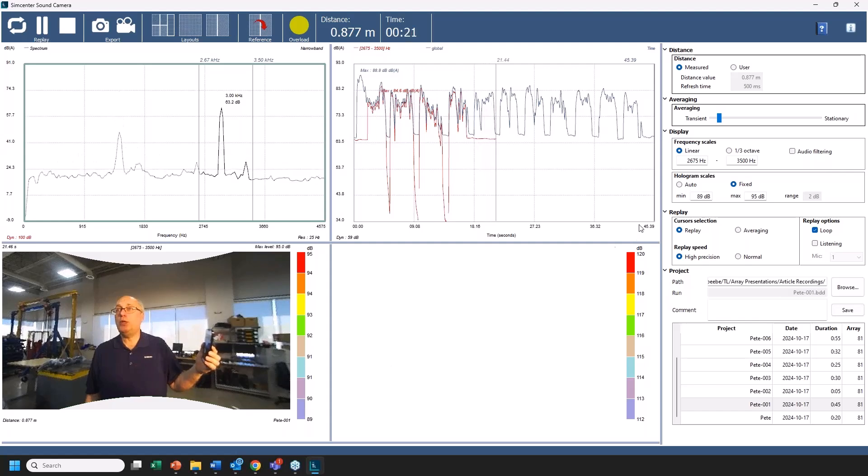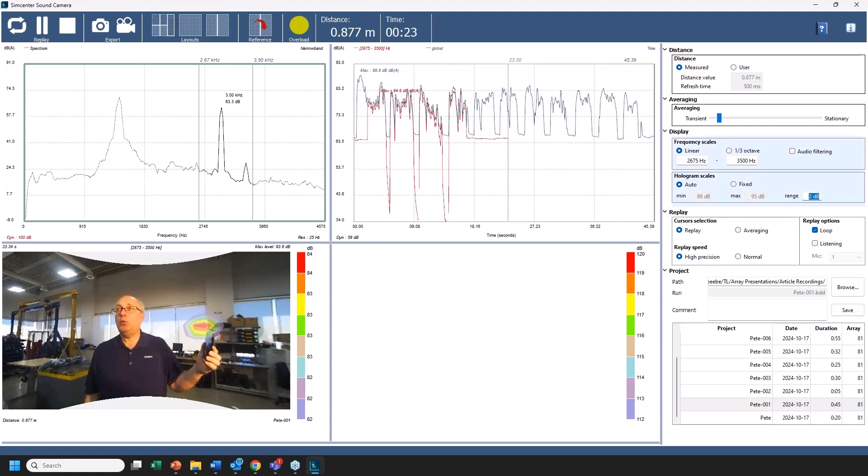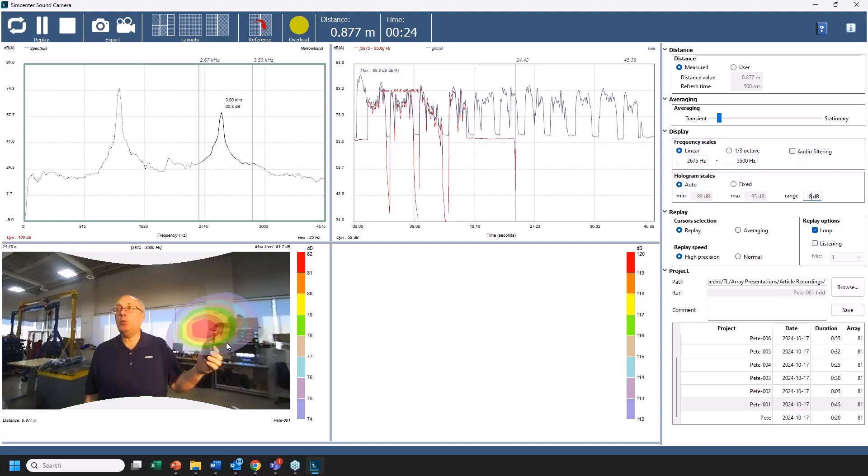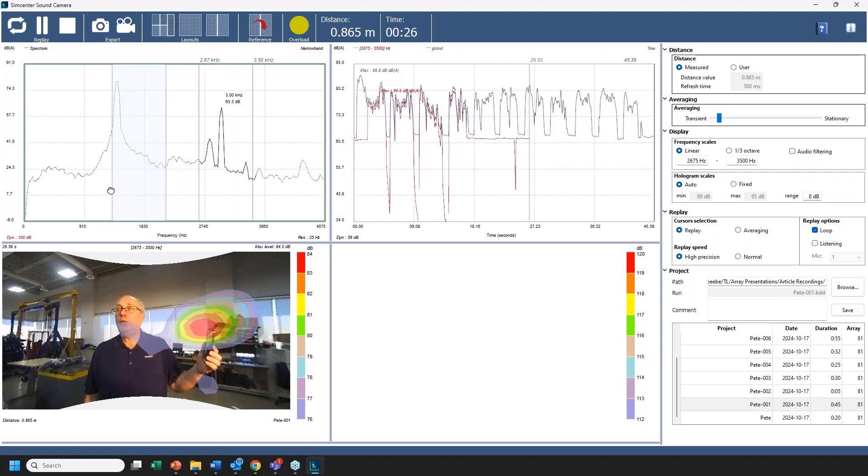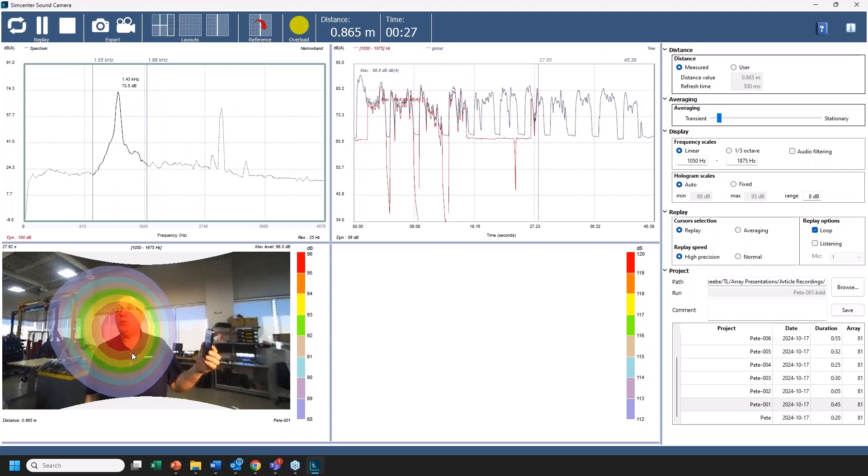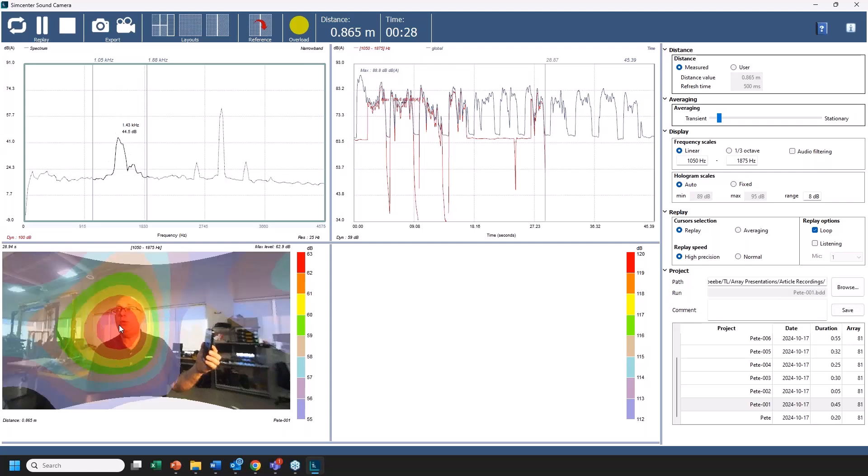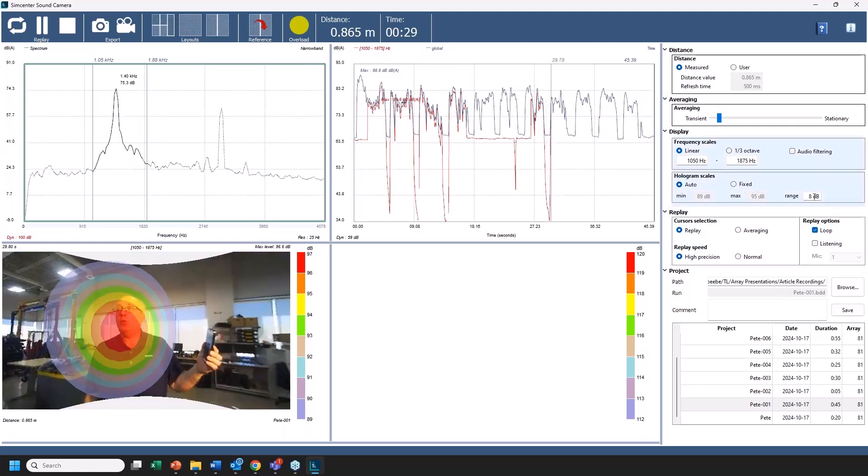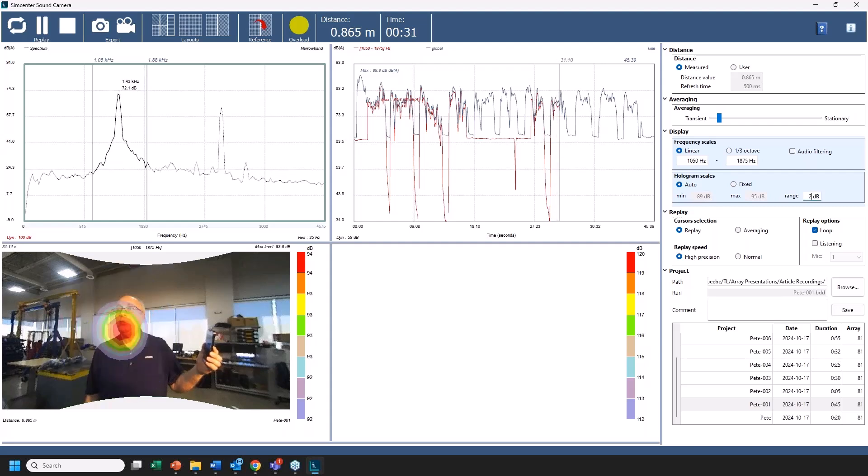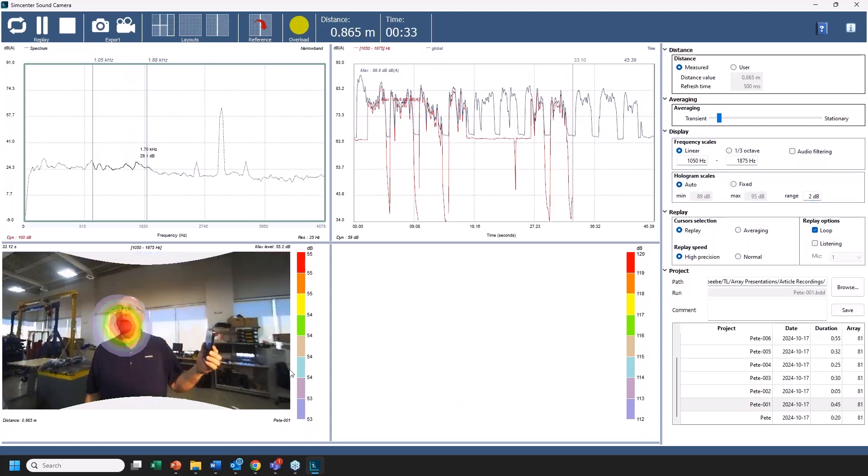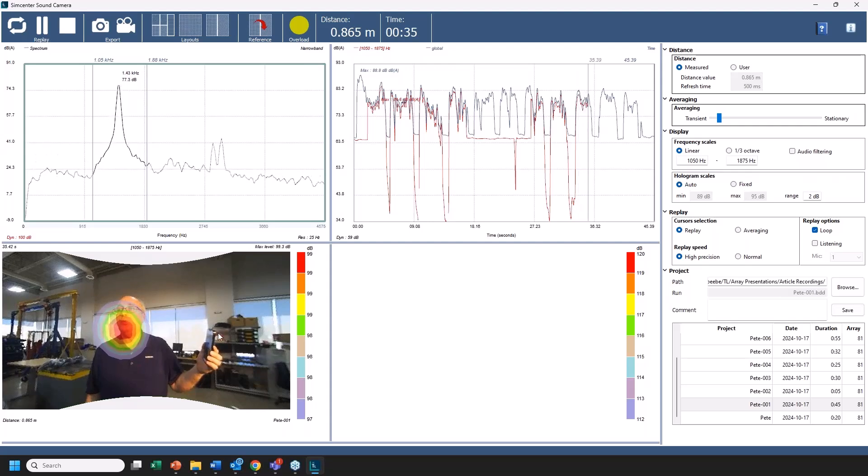Now we can go back to an auto scale and I'll show you a couple tricks here too. So by default in the software we have an 8 dB range. It just got bigger where that sound source was. That's right, and it'll get even bigger here if I switch it to the whistle. So again, if I want to reduce that overall size of the source localization, I can play with this auto range and reduce that range from the highest source down to the lowest source. In this case I'd use a 2 dB range. Zooms in a little bit more, huh? Yeah, you can zero in a little bit more when you change that scale.